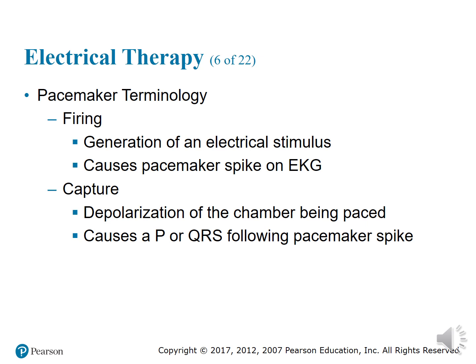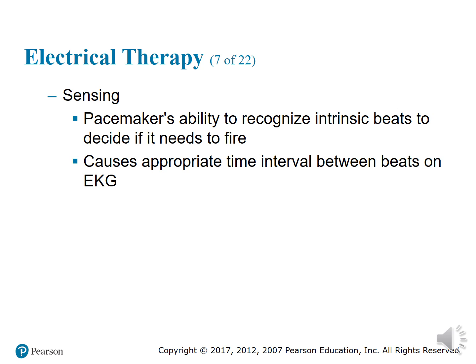Capture refers to the presence of a P wave or a QRS complex or sometimes both after the pacemaker spike. This indicates that the tissue of the chamber being paced has depolarized. Paced QRS complexes are wide and bizarre and resemble PVCs. Sensing. Sensing refers to the pacemaker's ability to recognize the patient's own intrinsic rhythm or beat in order to decide if it needs to fire or not. Most pacemakers function in a demand mode, meaning they fire only when needed, only on demand.